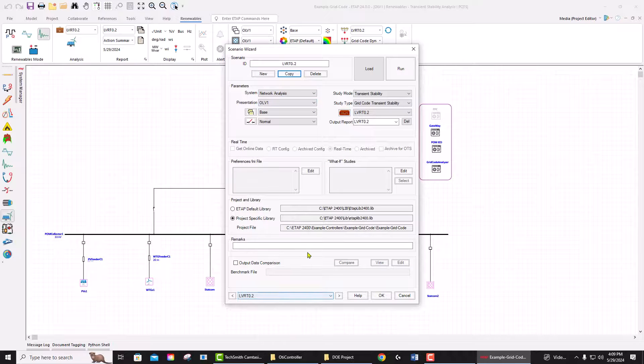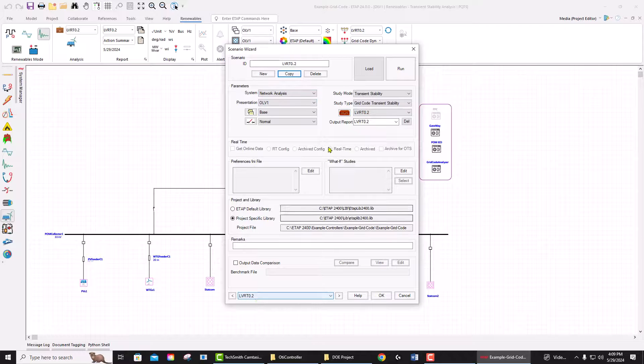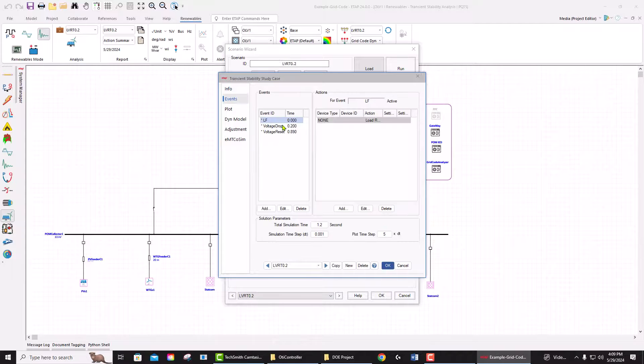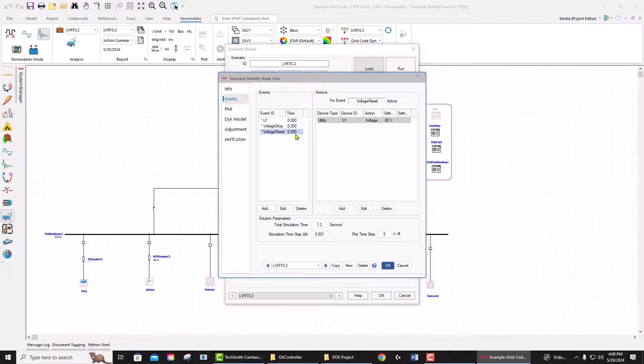This scenario is going to apply events to drop the voltage to 20%, so it's going to drop it by 80%, and it's going to reset the voltage back to one per unit. This is done at point 2 and point 89 seconds. If I run this scenario, it's going to run transient stability, and once it's done, it's going to...